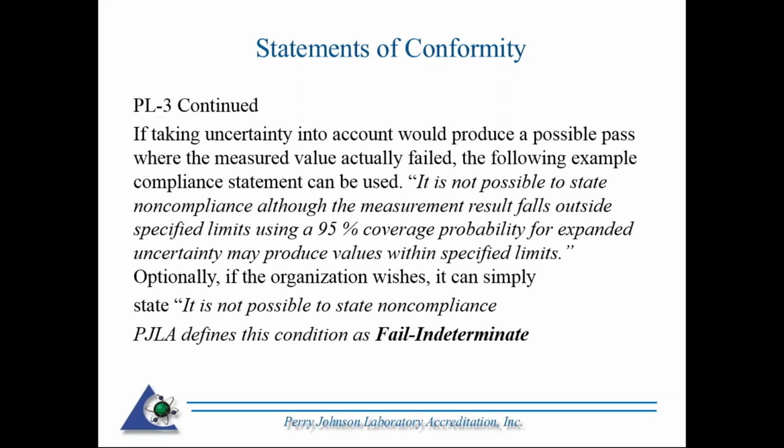So these are those conditions where the recorded value is very close to the tolerance limit, and uncertainty may actually cross over that. We also define this condition as fail indeterminate.